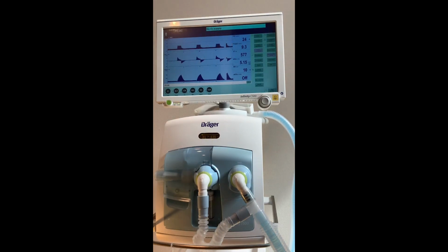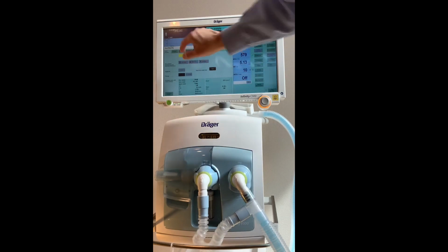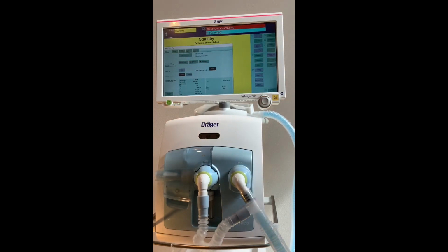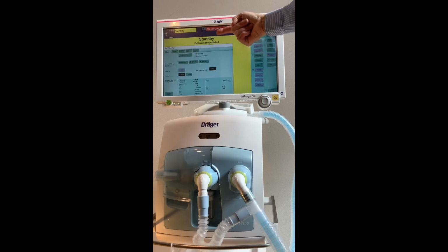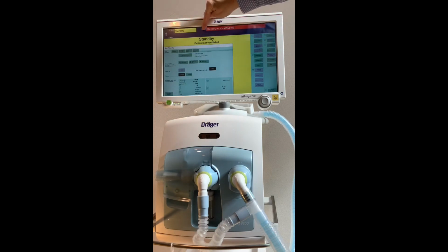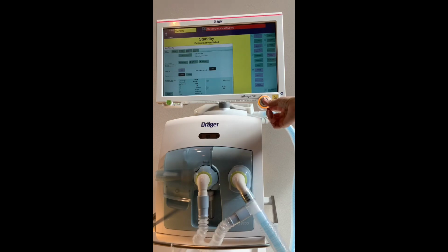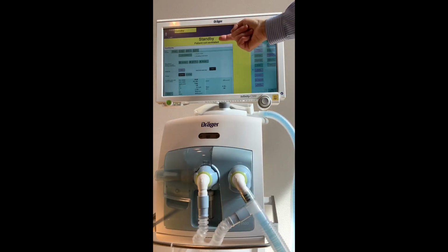To stop ventilation, you simply touch the Start Standby tab in the lower right-hand corner of the screen. You then touch the standby bar and confirm. Your patient is now not being ventilated and the machine is in standby. You must confirm by touching the alarm reset and using the rotary knob to confirm. And now the patient is not being ventilated, the machine is in standby, and it's ready for use.